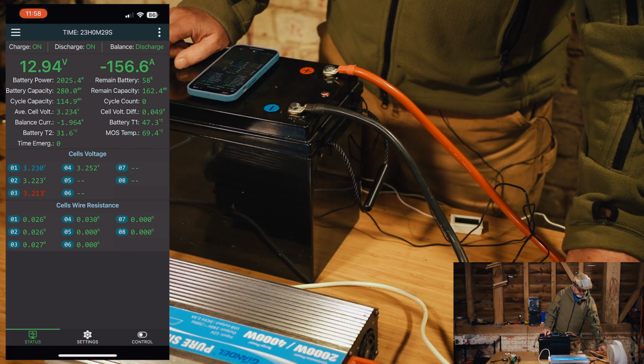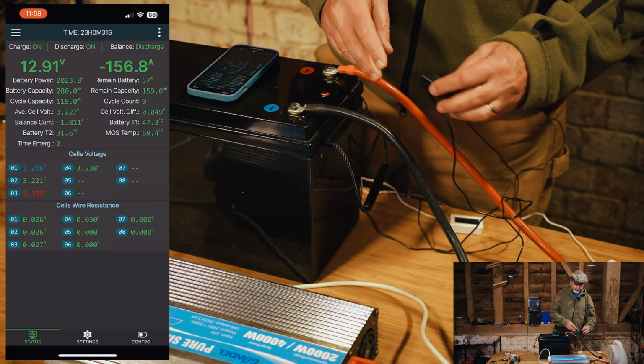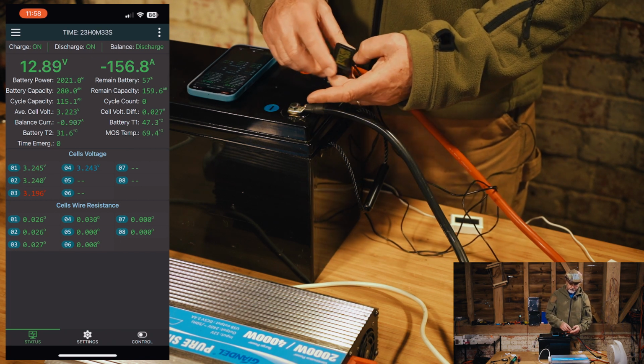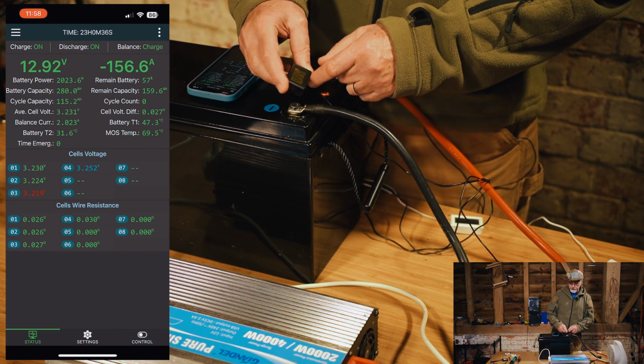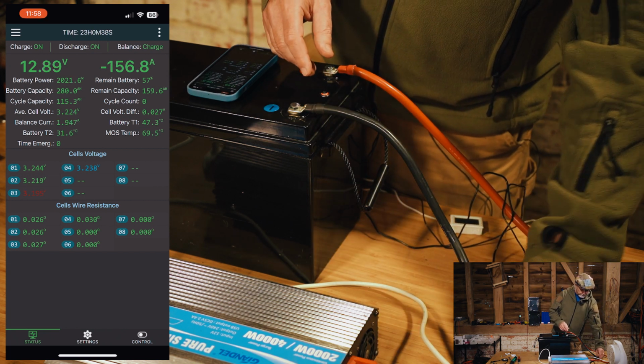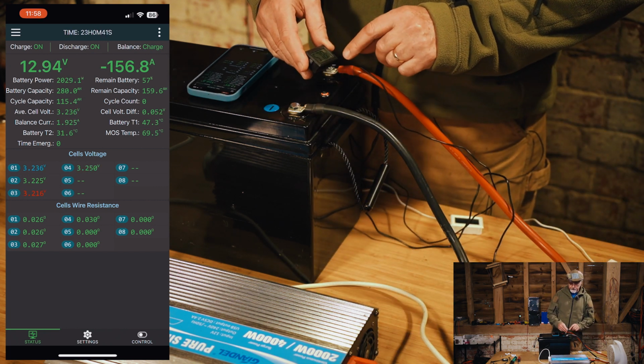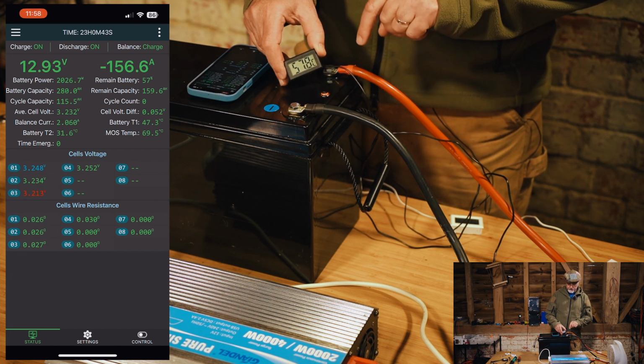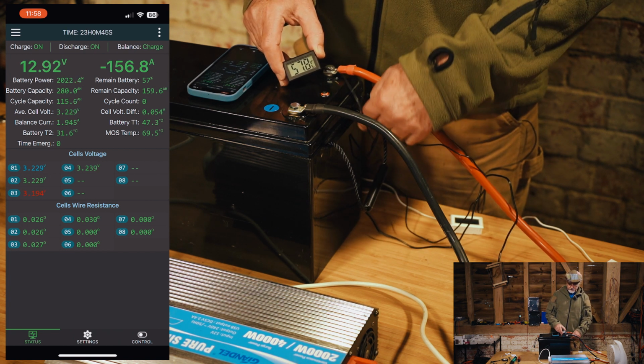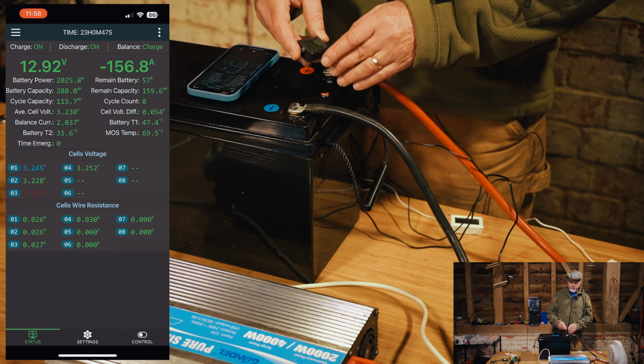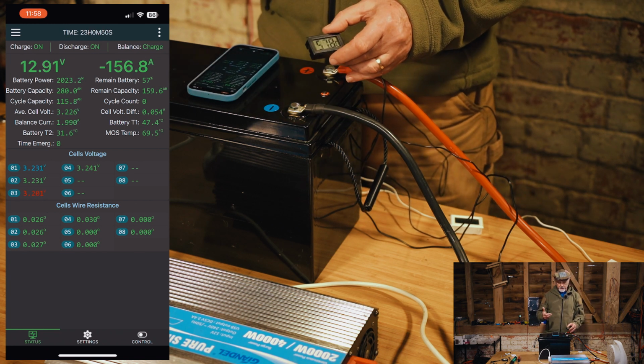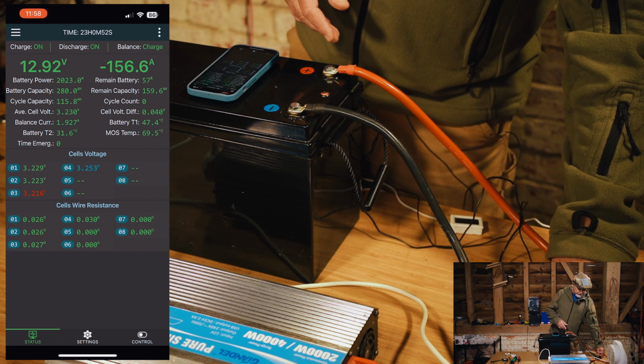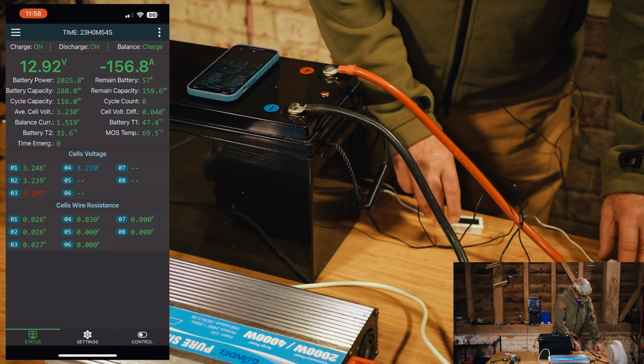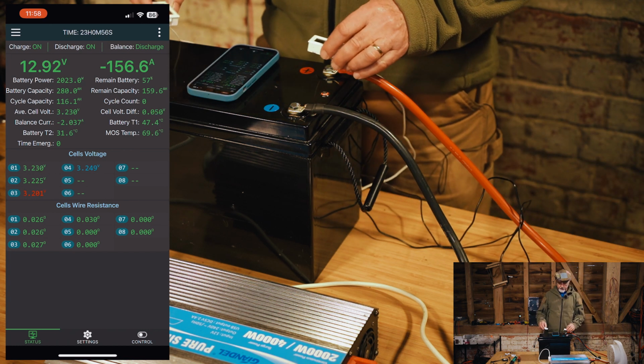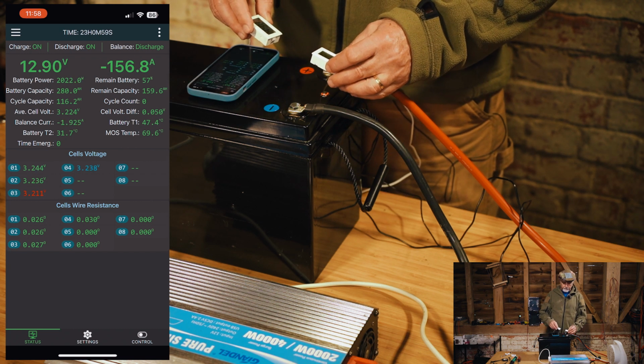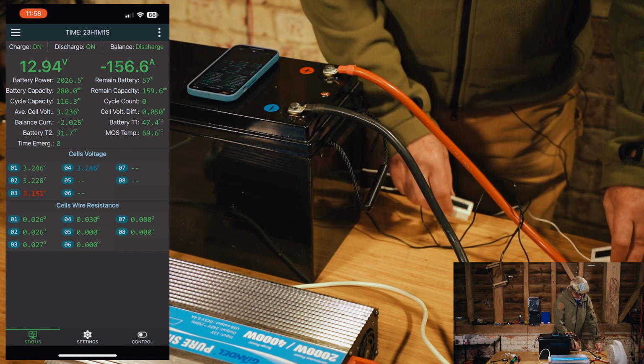Looking at these probes - this one running on this side of the BMS is at 49.5, so not heating up much more. This one's at 57.8, running along this side, so the connection here is a bit warmer, generating some heat. It would be good to get the whole pack out and measure just how much heat it's generating. Elsewhere on the pack and the bus bars, we're at 44.4 and 49 degrees centigrade.